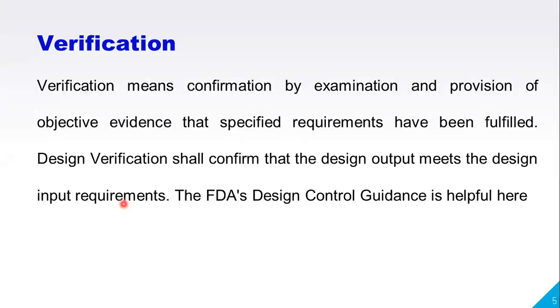Then coming to the detail, what is verification? Verification means confirmation by examination and provision of objective evidence that specified requirements have been fulfilled. That is a simple one. Design verification shall confirm that the design output meets the design input requirements. That is this one, very simple. The design output meets the design input requirements.